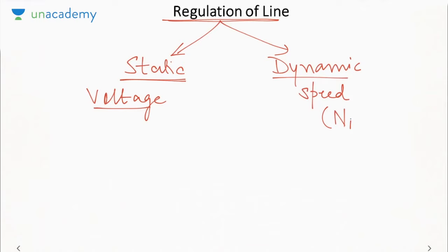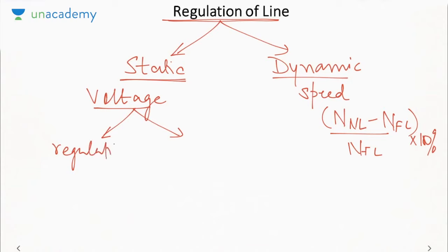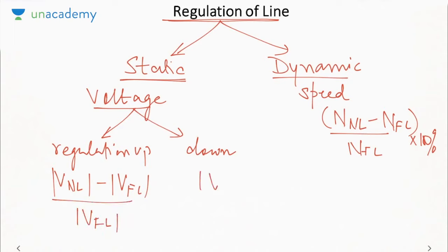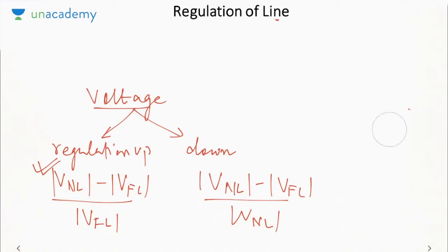Wherever the output is mechanical, we define dynamic regulation or speed regulation. Okay, this is simply no load speed minus full load speed by full load speed into 100. So remember, for the case of motors, we cannot define the voltage regulation. That is only defined for systems which have electrical output. Now voltage regulation can also be divided into two parts. One is your regulation up and regulation down. For up it is no load voltage minus full load voltage by full load voltage. For regulation down it is no load minus full load by no load. For the case of power system we will use the regulation up. So every time we calculate the voltage regulation, it is always calculated at the output terminals of a system. So like for the case of a transformer, voltage regulation will be calculated at the secondary winding because output is taken across the secondary. For a generator it will be taken at the terminals.